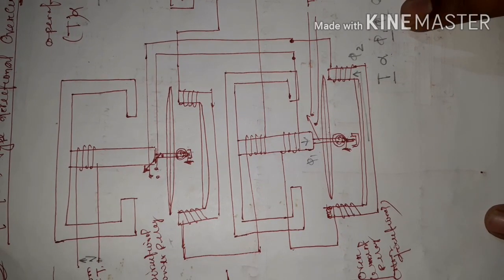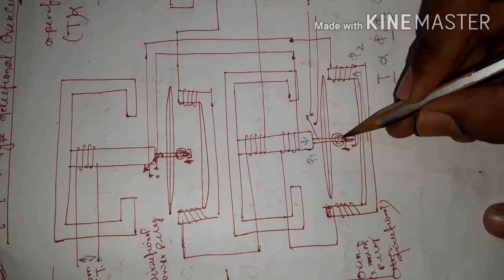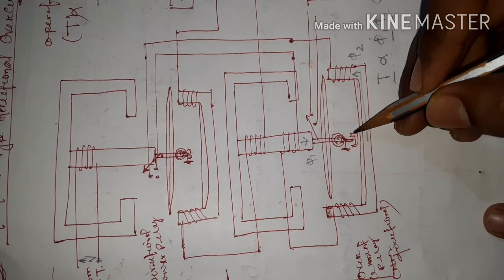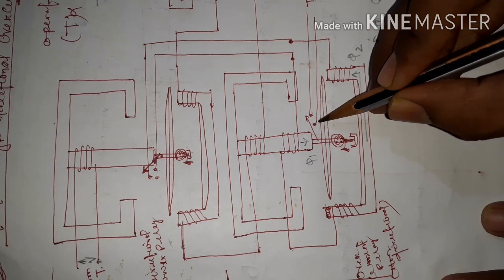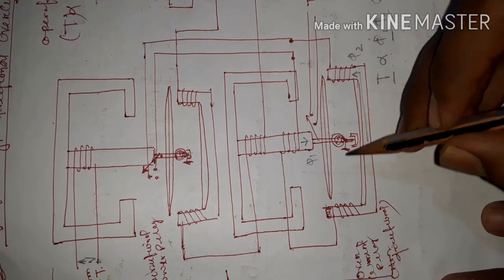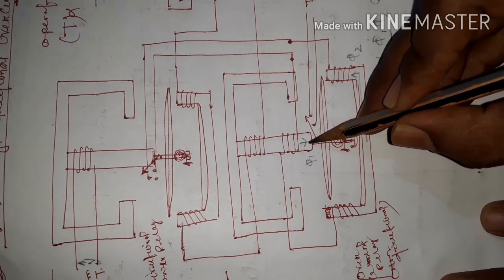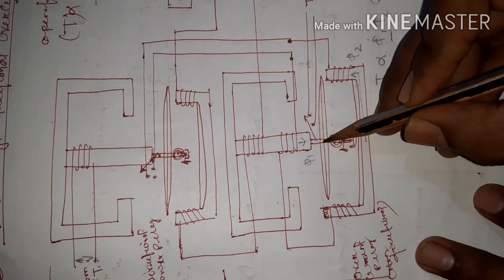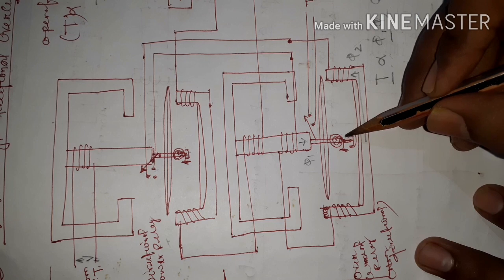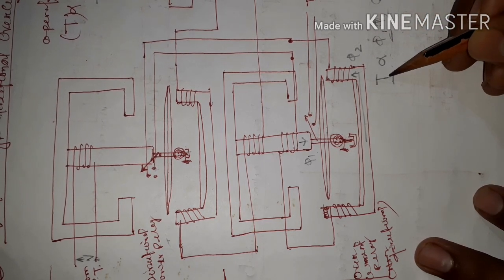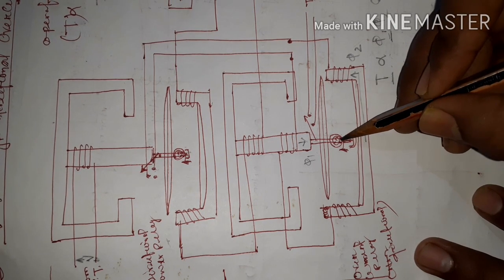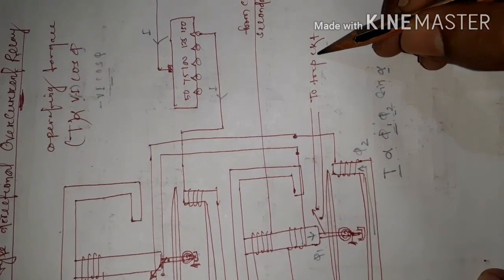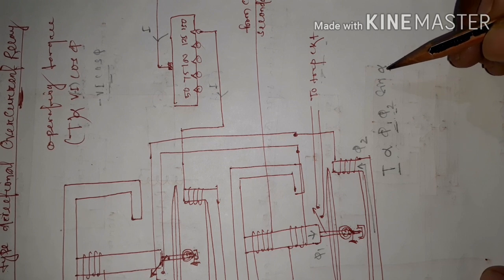When this operating torque is greater than the restraining torque provided by the spiral spring, the aluminum disc rotates in the clockwise direction and closes those two contact points. Under normal operating condition the operating torque from the interaction of φ1 and φ2 is not sufficient to rotate the disc against the restraining torque. But when a fault occurs, the two fluxes develop an operating torque whose magnitude exceeds the restraining torque, so the disc rotates clockwise, closes the contacts, the trip circuit is activated, and the trip coil is energized.